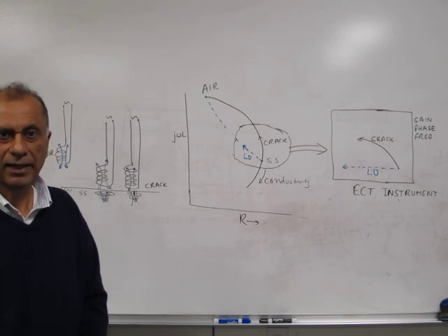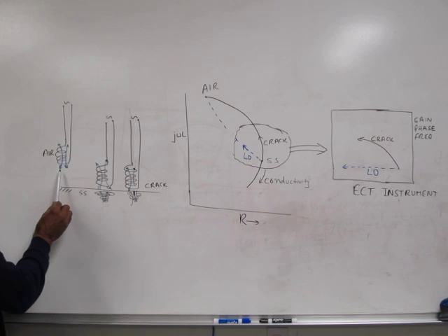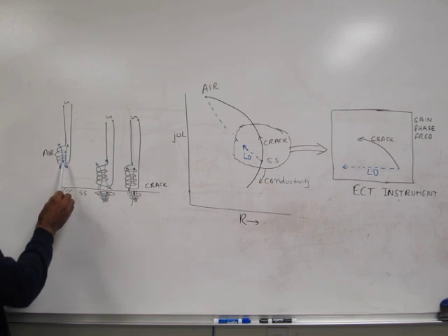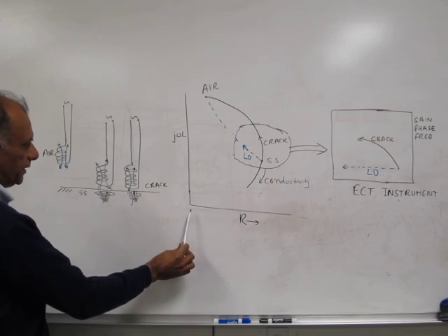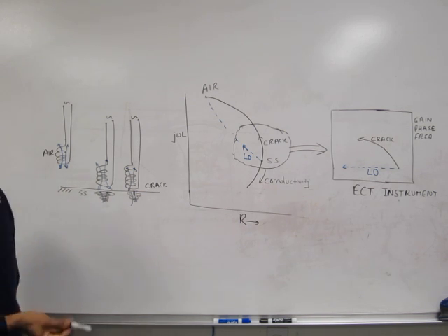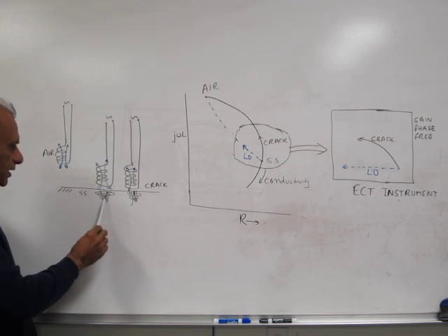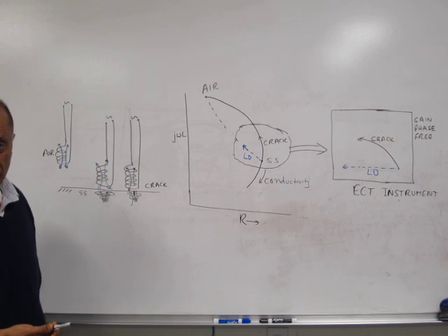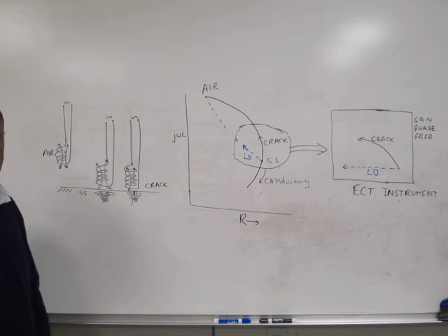The eddy current machine measures the changes in impedance of the eddy current coil. Here is an eddy current coil in air — it produces a magnetic field shown in blue color. When the coil is in air, the impedance of the coil is displayed on the impedance plane diagram at a specific point. When the coil is lowered onto the surface of a conductive material such as stainless steel, eddy currents are produced in the material, generating a magnetic field that opposes the primary magnetic field of the eddy current coil.